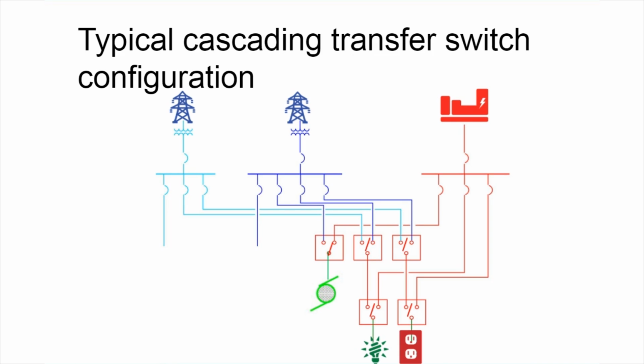Another approach, again providing a higher degree of reliability, is cascading transfer switches. So you may not do this for all the loads in the building, but maybe it's for the life safety. In healthcare, we often do it for the critical loads as well, where you've got two sources of normal power, and then you've got your standby generators, emergency generators. The utility sources would feed one transfer switch, which would then feed into the second transfer switch. So now we have to lose two sources of power before we have to go on to emergency power. Again, looking at level of redundancy and reliability, it all depends on your owner's requirements.